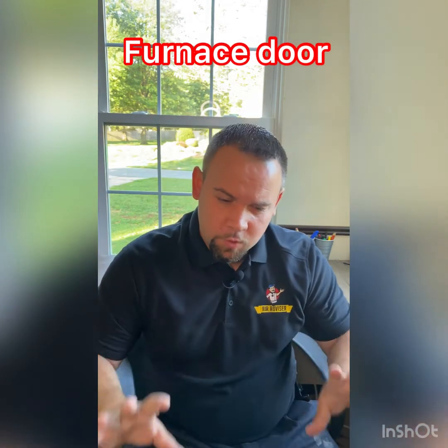And another really simple thing that you can check, but it's a little bit more uncommon, is if you're still not getting the unit to come on, you can always check the front door of the unit. If the front door of the furnace is not snugly up and latched in 100%, that would definitely cause a power issue, because there's a safety door switch inside the furnace that would not allow power to work. And that's it, guys. That's a little rundown of just basic little things that you can check to make sure that you're not going to have a silly little nuisance breakdown, which happens quite often, to be honest with you.